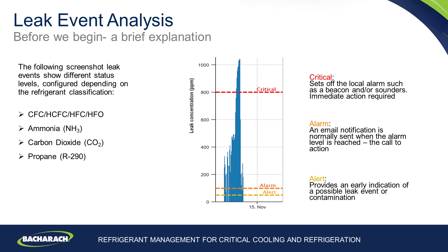At the alert level, leaks are going to be more difficult to find, but identification and rectification will mitigate any refrigerant loss or system performance impact. The alarm threshold is usually the call for an engineer to attend site. For HFCs, we're looking in the range of 80 to 100 parts per million. At this level the leak is still small, but should be easier for the engineer to find, identify, and fix, keeping refrigerant usage and loss to a minimum without effect on system performance.